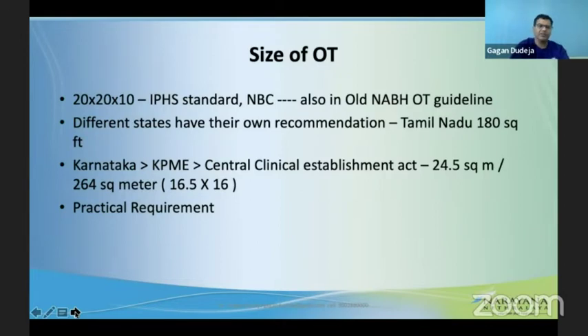The table size is 6 by 2. You would need at least 4 feet towards the foot end and 5 to 6 feet towards the head end, since you have to sit and trolleys and assistants need to come in. You also need 4 feet on the sides for another trolley to move and the door to open. Adding it up—6 plus 4, 10 plus another 5—you get 15 to 16 feet in length. Anything less becomes cramped.